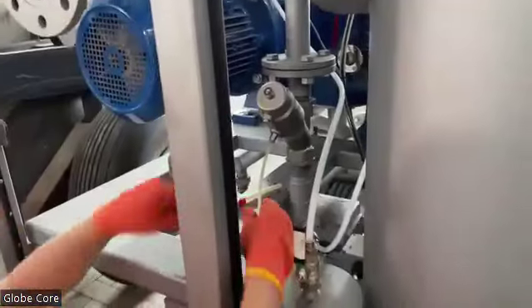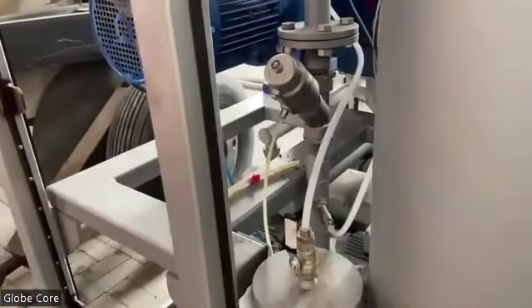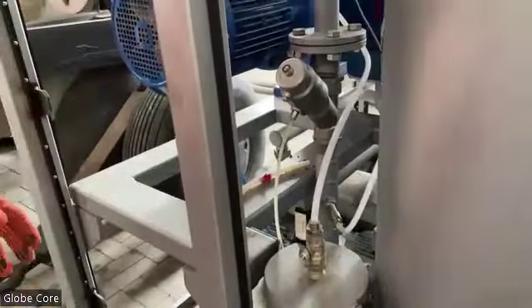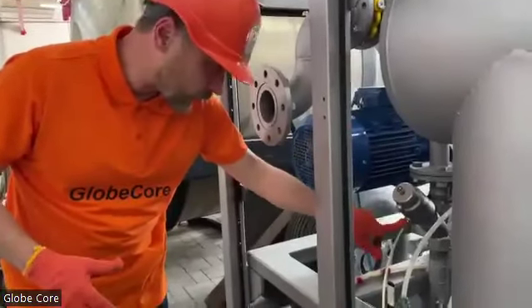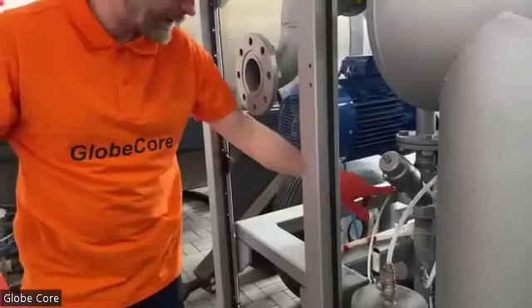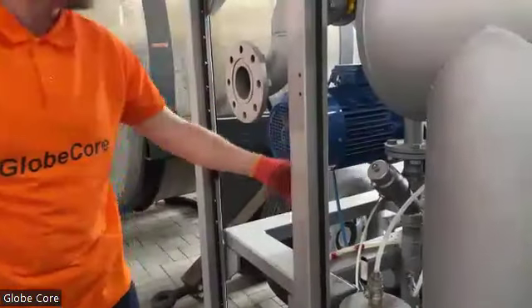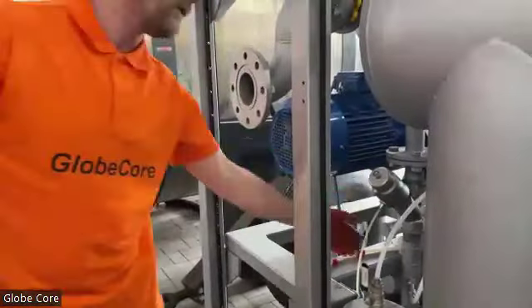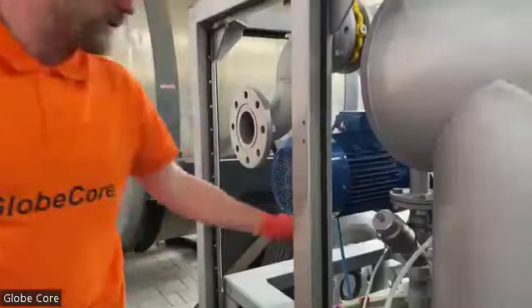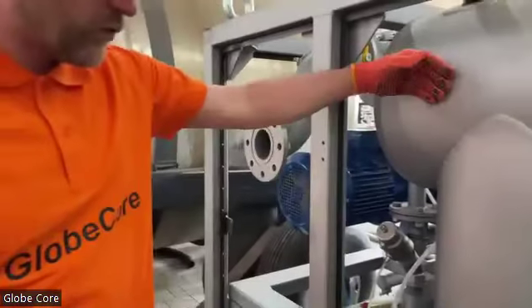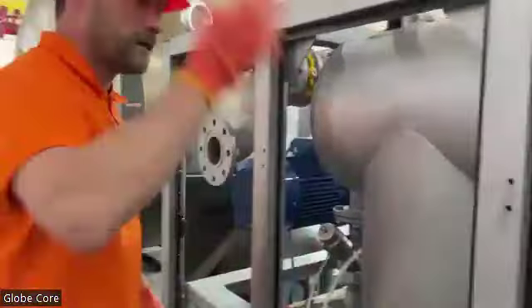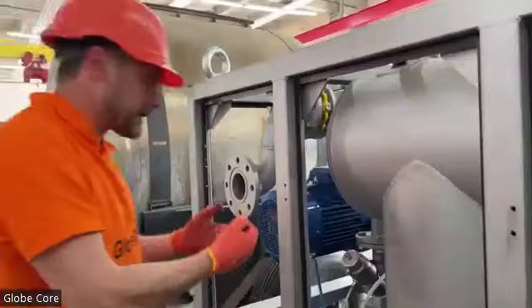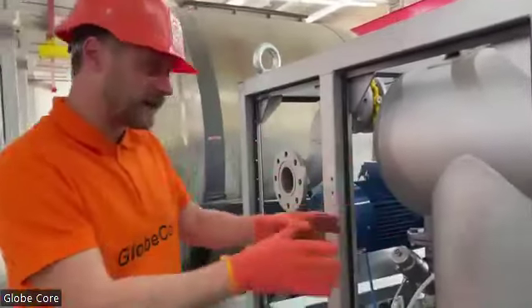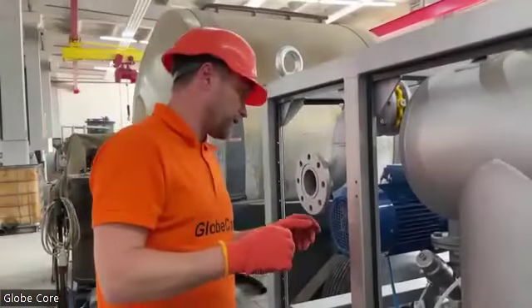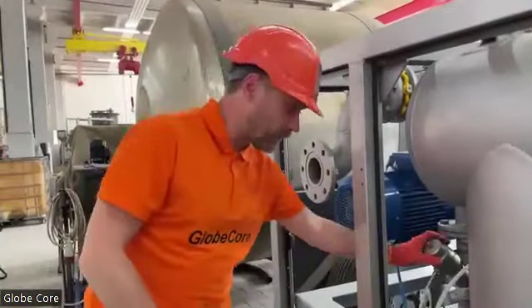So pressure in here is provided by operation of the inlet pump. If the pump works, it provides pressure on this point of the valve, and it makes the valve open. So oil finally goes into the vacuum chamber. This valve is used to prevent uncontrolled filling of the vacuum chamber, since here we have a low pressure and oil will be sucked by itself into the vacuum chamber. To prevent uncontrolled filling of the vacuum column, we use this cutting off valve.